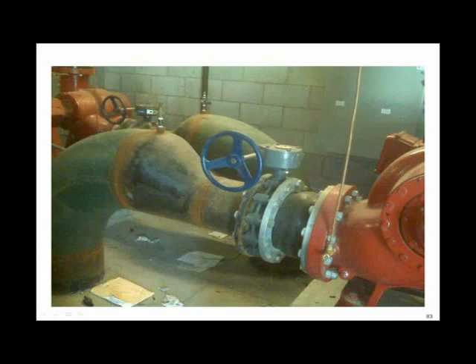This is the one I was telling you about that broke the shafts. And it ain't our fault when you do things like this, guys. You got to help us out a little bit. You got to recognize it's not unusual to have slightly negative pressures on the suction side of a pump. And you're going to always have air. So those are two things you got to deal with, and we can't change the basic laws of physics. Hopefully your jobs never look that way.